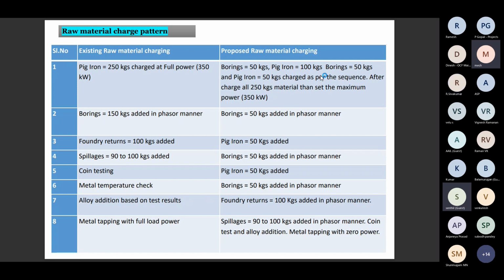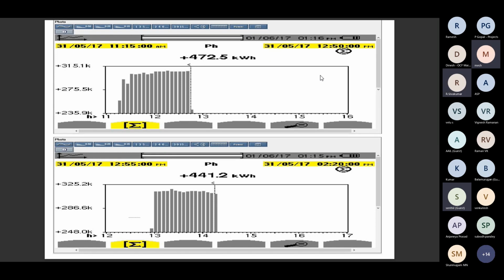Next. So in the existing pattern, this graph is from the power quality analyzer we have. There are energy and power quality measurement instruments we have through our project. I studied the existing practices. For one melt, it takes around 472.5 kilowatt hours for melting almost 550 to 580 kgs of raw material. Molten metal of 570 to 580 kgs was taken at the 350 kilowatt furnace. For one batch, it consumes nearly 472.5.